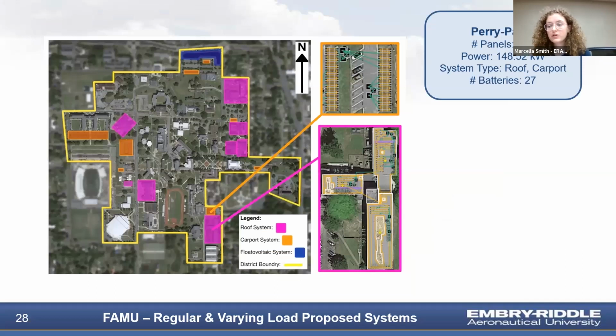Perry and Page, while their energy load consumption data was provided separately, have perfectly matching loads, share a meter and transformer, and have no clear distinction between rooftops. We combined their systems into one, which features 316 panels, producing 148.52 kilowatts and charging 27 batteries. Perry and Page are supported by a rooftop system and two carport systems in the parking lot directly north of the building. Now Ian will discuss distribution impact.